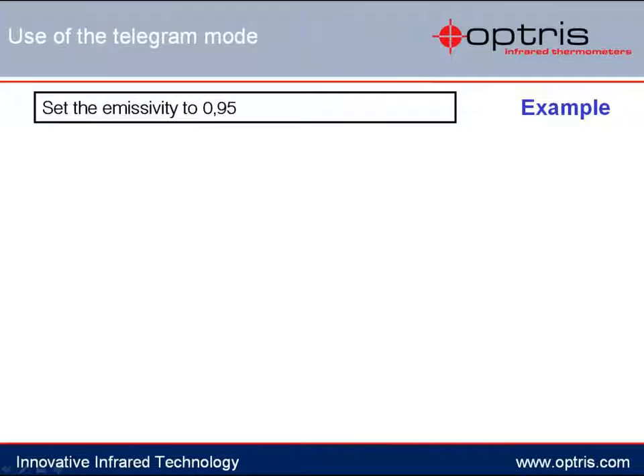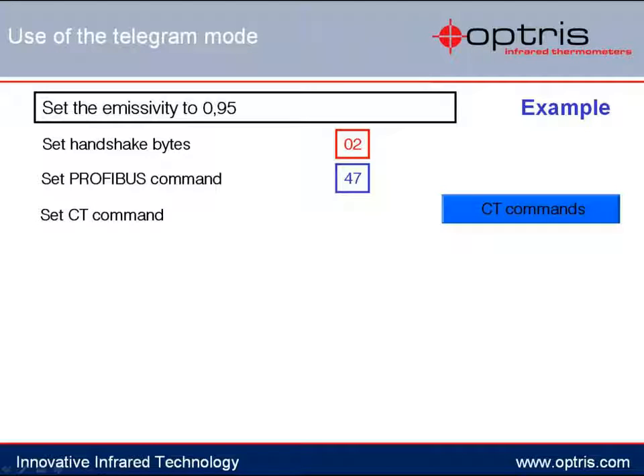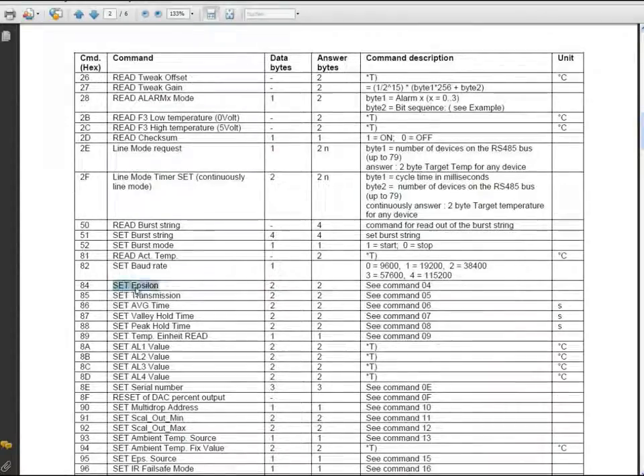Let's look at an example. In this case, we will change the emissivity of the temperature sensor to 0.95. The first step is the sending of a handshake byte — in our case, this byte has the value 02. The second byte is the PROFIBUS command 47, which informs the temperature sensor that another command will be sent. The third byte includes the actual command specifying which settings will be changed. Looking at the command list, to change the emissivity of the sensor, command 84 is needed.